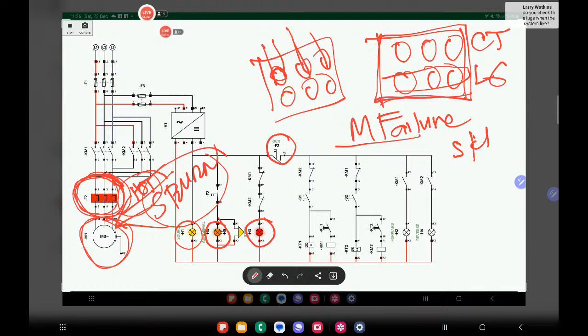your, what do you call this? Your terminals are intact. You did a continuity test that all the windings are okay. And then line to ground is healthy. You don't have earth fault. You try to run by hand and it's rotating. It means the bearings are in good condition. So there is no way that the system will overload unless there is a single phasing on the system or on your contacts, right?